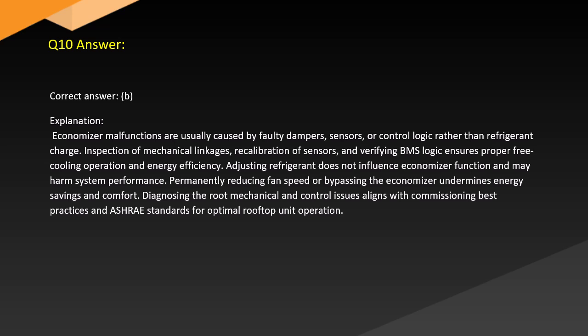Permanently reducing fan speed or bypassing the economizer undermines energy savings and comfort. Diagnosing the root mechanical and control issues aligns with commissioning best practices and ASHRAE standards for optimal rooftop unit operation.